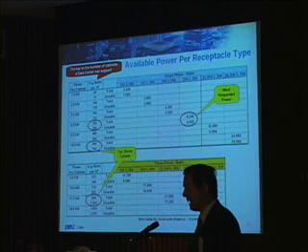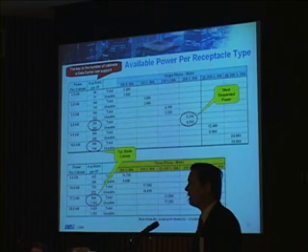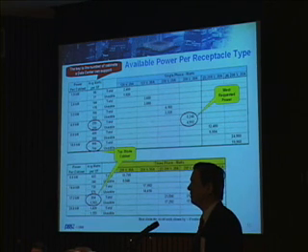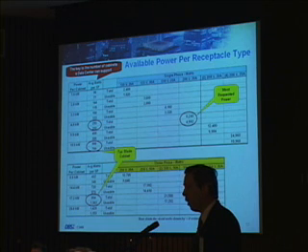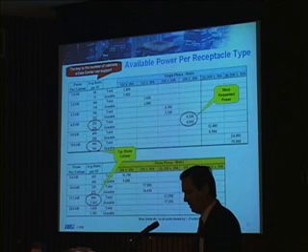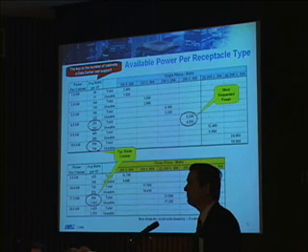What we see is most cabinets are looking at about 30 amps worth of power going to a cabinet, and that's about 200 watts per square foot. Most data centers are built anywhere between 50 and 80 watts per square foot. Some of the newer ones were built for 120 watts per square foot. So most data centers cannot support the watts needed for a cabinet under today's high density needs. If you go to blade server cabinets, you're up over 800 watts per square foot.